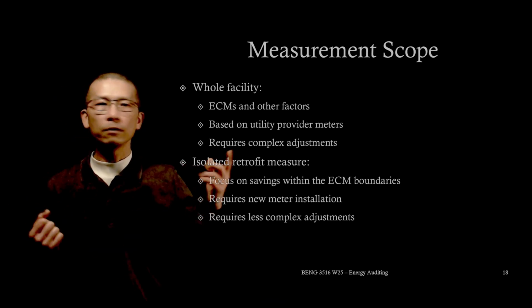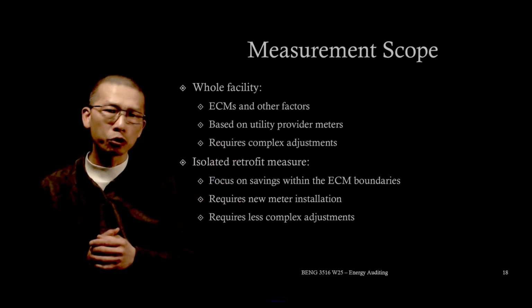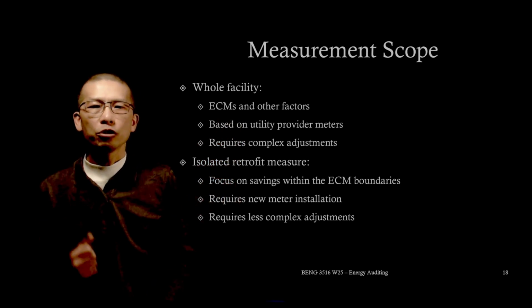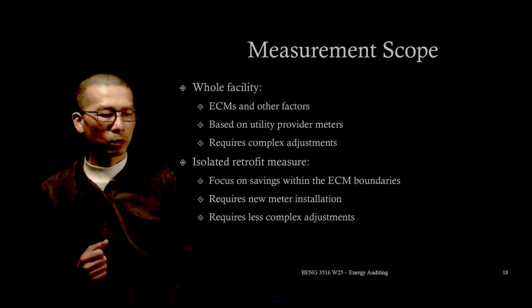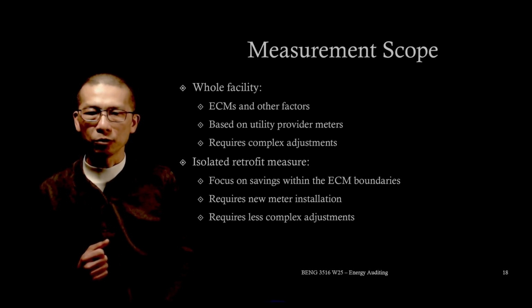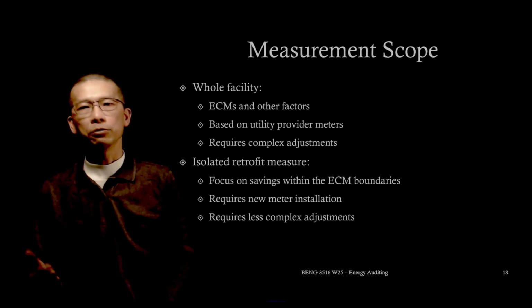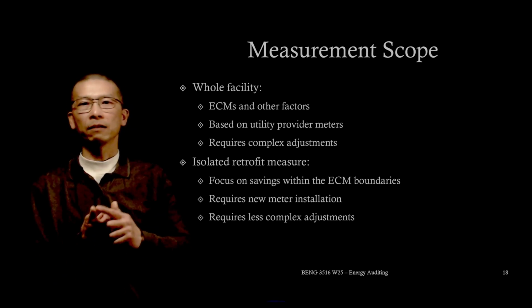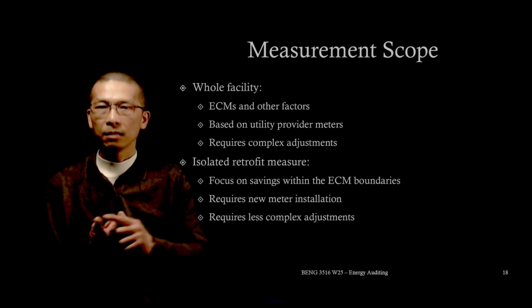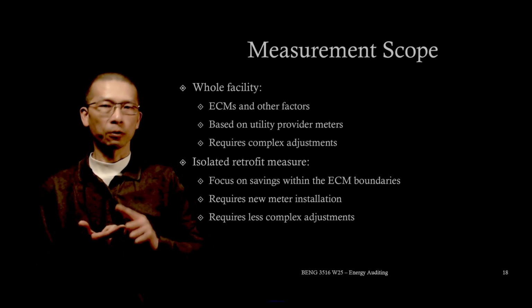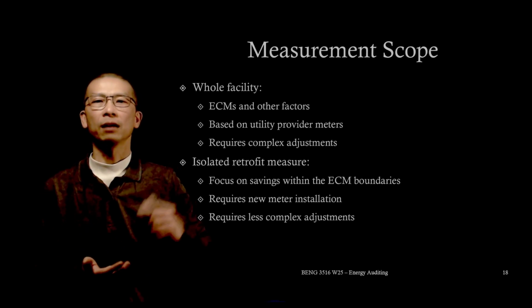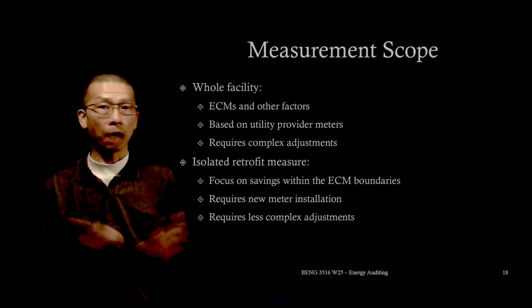For the whole facility approach, it measures the total energy consumption of an entire building or entire facility. It includes the impact of the ECM plus other external factors like weather, occupancy, operational changes. How is it measured?